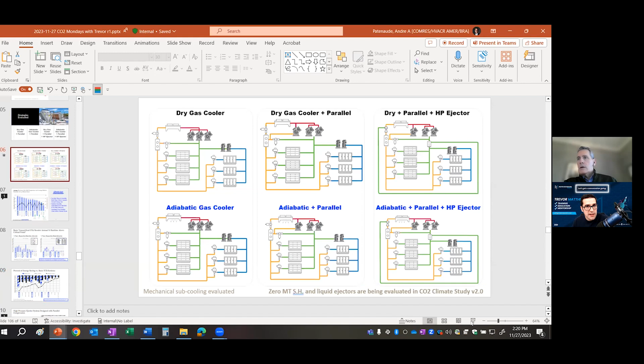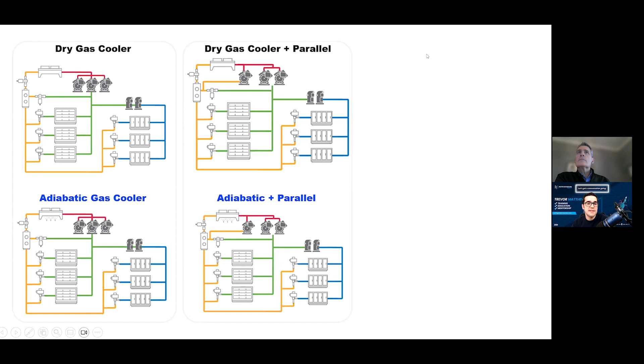And if I can share a chart here, the reason that I think we're going to see more of that, let me see, share. Because really with parallel compression, when you have all that flash gas coming out of that fluid in the middle of the summer, you get more gas coming out of the fluid into your receiver, your flash tank. Instead of just putting it into your medium temp suction, you actually have another suction at a higher pressure, which reduces that pressure ratio or compression ratio, where now you can save energy on the system.